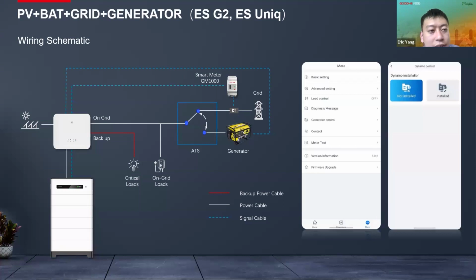It means in this system we will have a third-party EMS, and the connection is like the diagram. The on-grid side will connect to this ATS, and one side is connected to the grid, and the other side is connected to the generator. When the grid is available, the inverter on-grid port will connect to the grid. The logic we have introduced just now: the PV will support the loads first, then charge the battery. Also, it can feed power to the grid. And when the grid fails, the ATS will switch to the generator port, and the inverter will send the signal to start the generator. Then the generator starts to work.